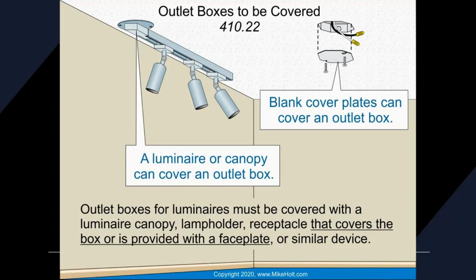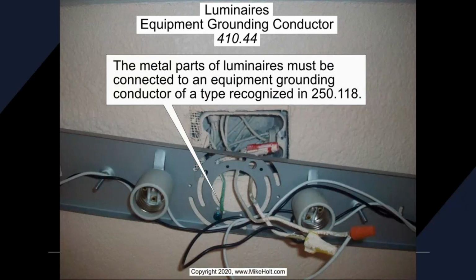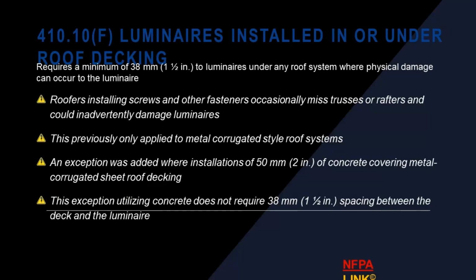All right. Luminaires, equipment grounding conductor. All the metal parts of a luminaire must be connected to an equipment grounding conductor of a type recognized in Article 250.118. All right, so we want to maintain that low impedance path back to ground. We're going to do that with this. If we have a short circuit to this light, we want a low impedance path back to ground. Again, there's a ton of luminaire questions in your homework. There's a whole section on this, so you might as well dig into 410.